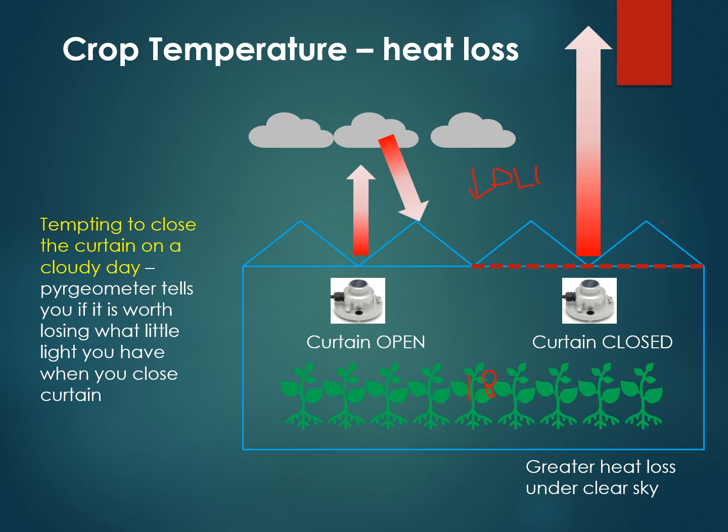We can float the temperature down, and if it's not cloudy, close the curtain because we know that the crop otherwise will radiate its energy up to the curtain, which to the greenhouse, and then that to the atmosphere, and then ends up costing you money to heat the greenhouse to maintain the temperature. So if we're at an acceptable light level with the curtain closed because we've lowered our set points, we're okay. The pyrgeometer helps us make that decision.